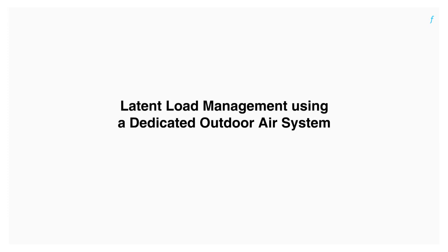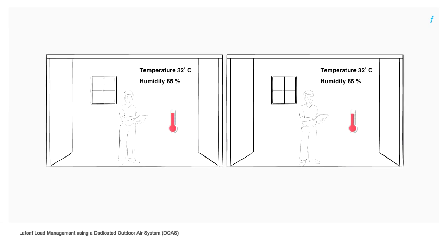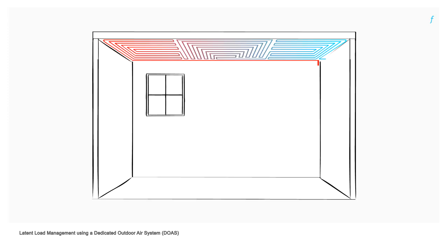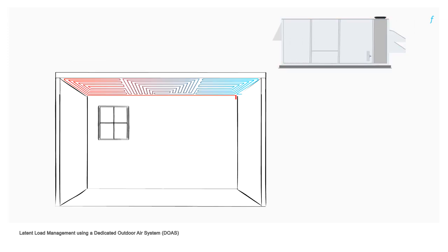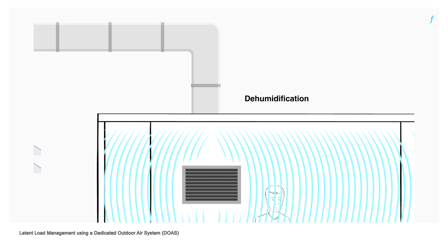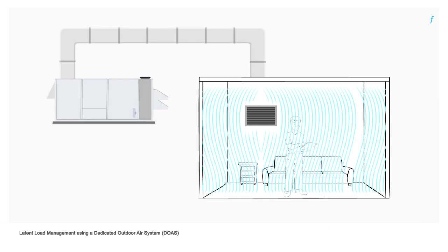Latent heat load management using a dedicated outdoor air system: Comfort is as much about humidity as it is about heat. While radiant panels take care of the heat in the air, a dedicated outdoor air system is essential to handle humidity in the space. Along with dehumidification, the dedicated outdoor air system accomplishes ventilation and filtration. The air quantity requirement in this system is much lesser when compared to a typical air-based cooling system.